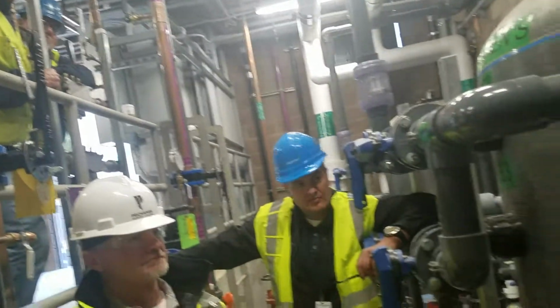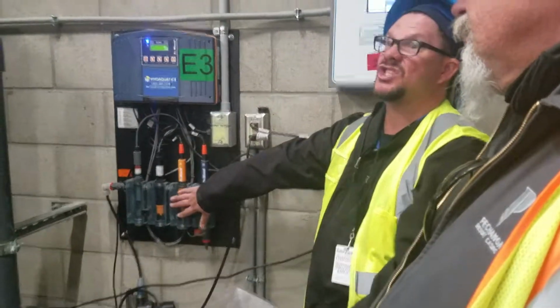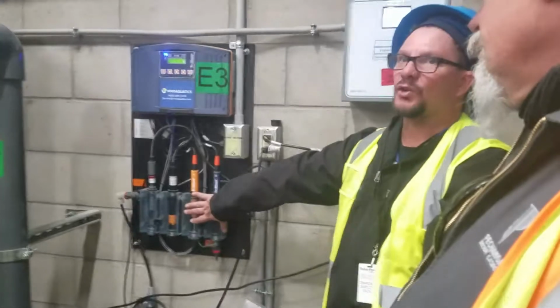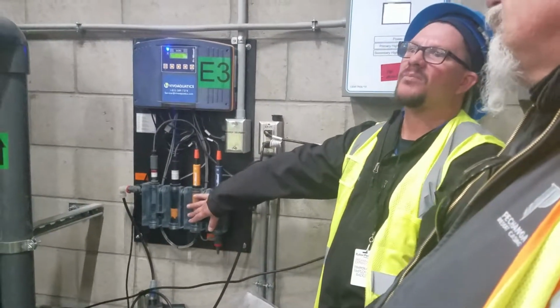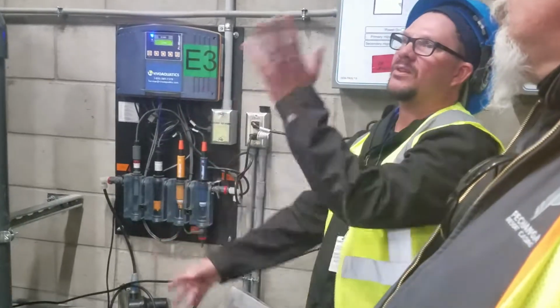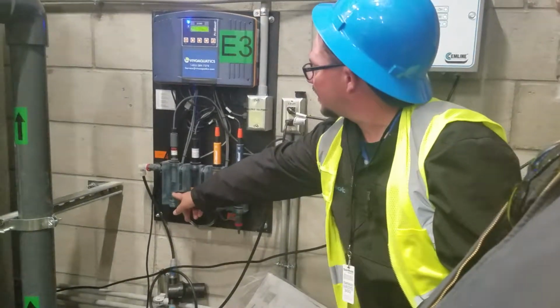So that's a great question, because you're going to want to validate that for sure. This has nothing to do with jet pumps whatsoever. It's all filtration. If somebody hits the emergency stop, the filtration pump should stop. You guys can verify that. And this is what we want to see happen. We want that to happen right there.